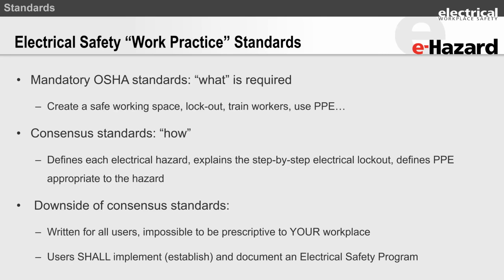So this now is very specific, because the consensus standard like NFPA 70E would tell you specifically this is the definition of a shock hazard. When a shock hazard exists at this many inches away from an energized conductor, here's the PPE that you need. And then they will go on to give you a step-by-step approach on how to create an electrically safe working condition. So can you see the difference between OSHA? OSHA cannot be specific. OSHA has to cast a wide net, because OSHA is looking at giving you the opportunity to use standards that work for you. They cannot be prescriptive. And I'll give you reasons why.